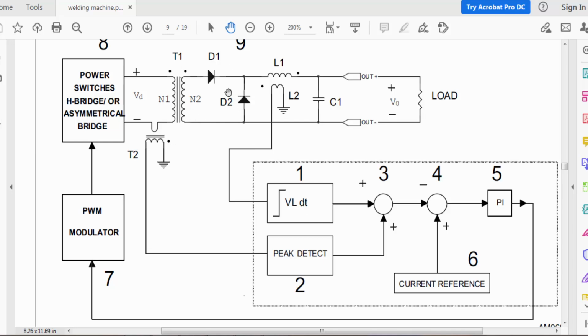If there is no good combination, there is a big difference between the primary current and load current, that means there is a short circuit and heavy current is flowing in the transformer windings due to a short circuit in the IGBTs or output rectifier, something is damaged or misbehaving.